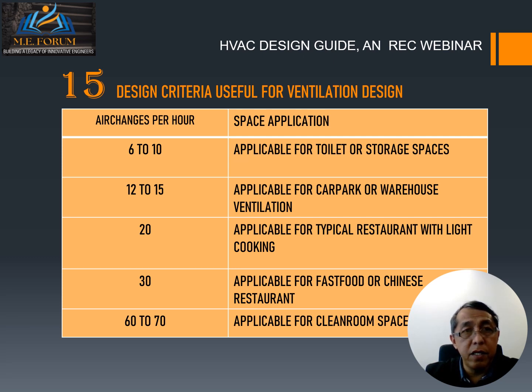6 to 10 air changes applicable for toilet or storage spaces. 12 to 15 air changes applicable for car park or warehouse ventilation. 20 air changes per hour applicable for typical restaurant with light cooking. 30 air changes per hour applicable for fast food or Chinese restaurant. 60 to 70 applicable for clean room spaces, but this comes with cooling.